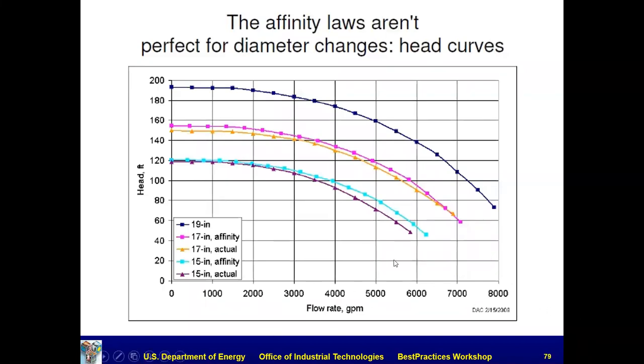And so here's some pump curves, and you can see, this is a 15-inch impeller. This is the actual curve that he tested, and this is what the affinity law said for a diameter change. Started at 19 inches, and say if you trimmed it to 15, this was what he measured, and this is what the affinity law projected. So, similar, but certainly not matching.